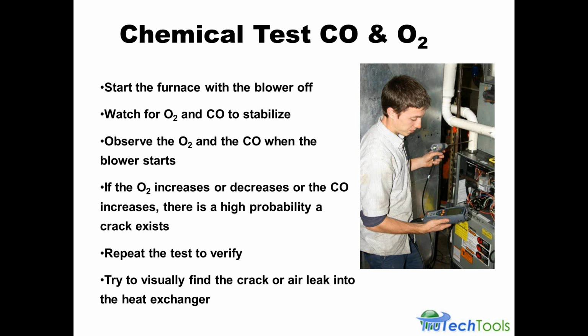If you're going to be doing heat exchanger inspections, you can do this chemical test. If it gets you on a trail of suspicion, then you crack open your book and take a look at what the common area of failure might be. Then you go look at it. It can save you tons of hours of inspecting a whole heat exchanger when you know where the common failure points are, and that's what this book does.